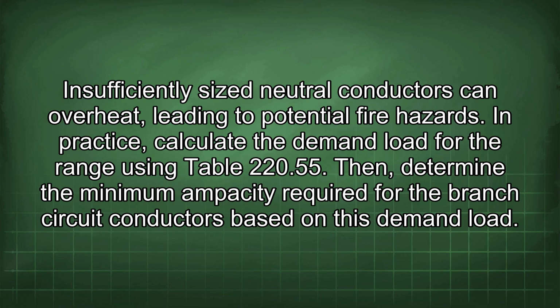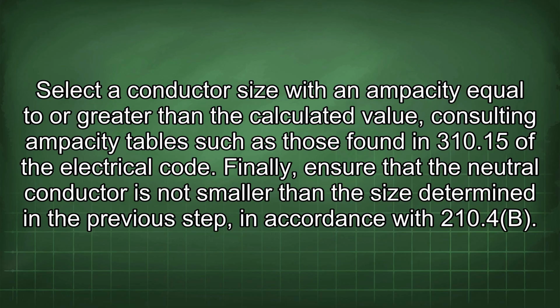In practice, calculate the demand load for the range using Table 220.55. Then determine the minimum ampacity required for the branch circuit conductors based on this demand load. Select a conductor size with an ampacity equal to or greater than the calculated value, consulting ampacity tables such as those found in 310.15 of the Electrical Code.